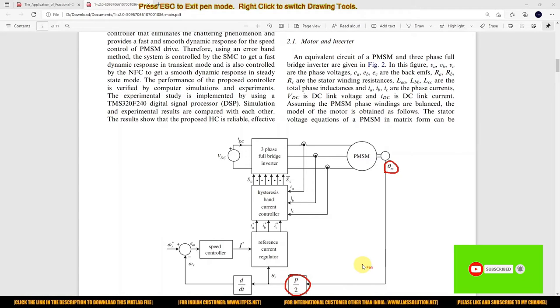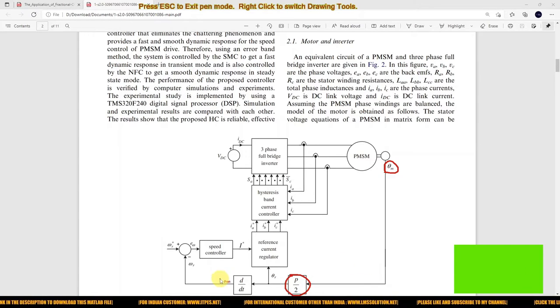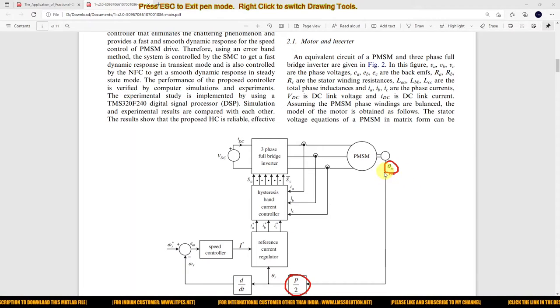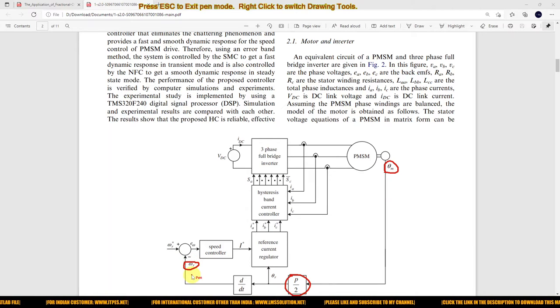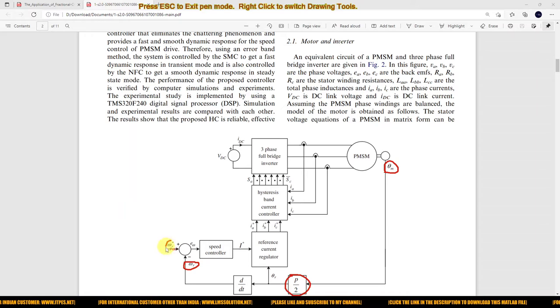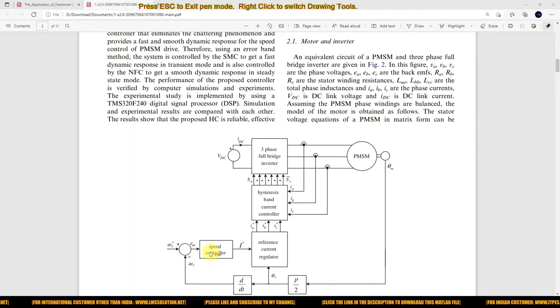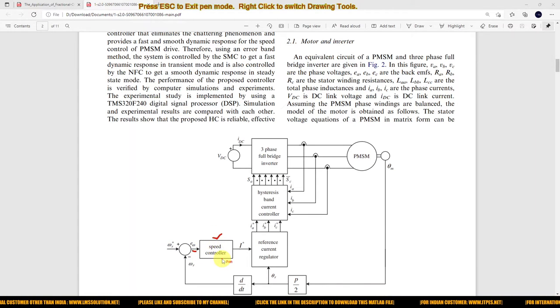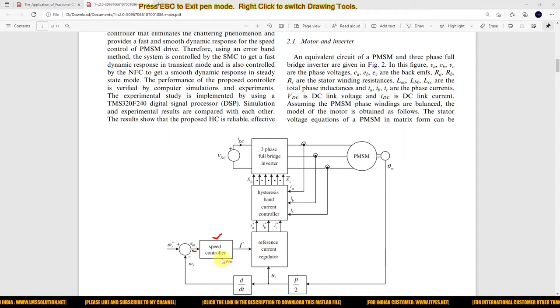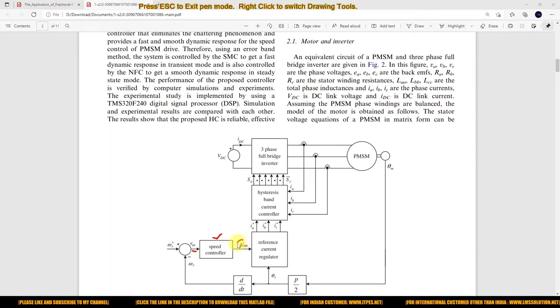Number of poles divided by 2. And then, based upon that rotor angle, we are measuring the speed — or else we can measure the speed directly. Then we need to compare with the reference speed. So this is known as reference speed, and the speed error will be processed via a speed controller. Normally we are using a PI controller.